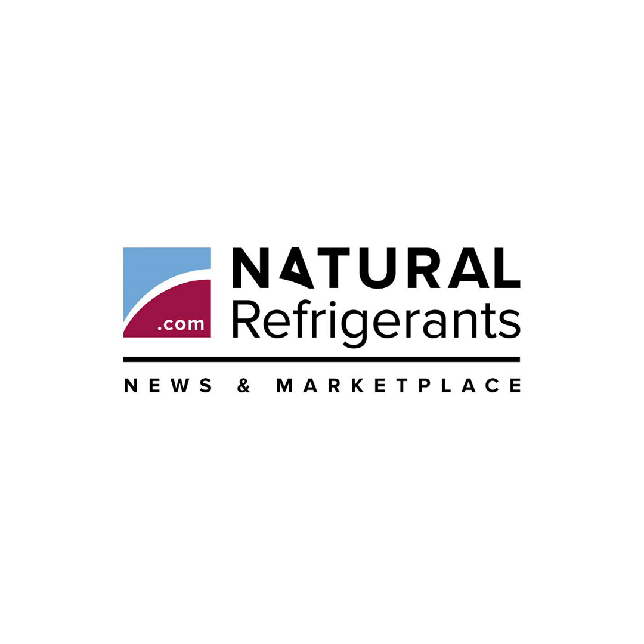Offering flow temperatures of 60 to 80 degrees Celsius, 140 to 176 degrees Fahrenheit, the units offer efficient alternatives to fossil fuel boilers as UK end users accelerate their decarbonization efforts, according to the manufacturers that spoke with naturalrefrigerants.com at the exhibition. Italian manufacturer Euroclimat also presented its isobutane-based commercial heat pump, which can provide hot water temperatures up to 110 degrees Celsius, 230 degrees Fahrenheit.